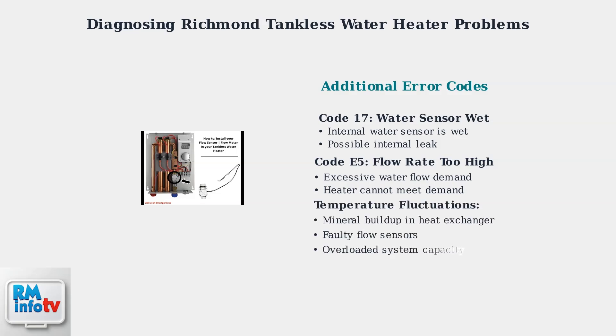Temperature fluctuations are another common issue, often caused by mineral buildup in the heat exchanger, faulty flow sensors, or an overloaded system capacity.